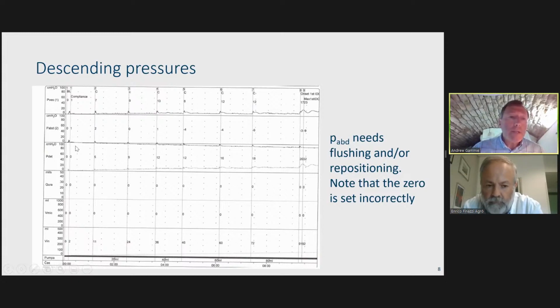But the point here is that it can also be seen that the abdominal line is descending slightly. Even though these little coughs are being picked up, the background resting pressure is going down. But our patient is not losing weight. There's no change inside them that is suddenly decreasing the pressure. So there's a problem. And for quality control, you've got to recognize that. And in this case, if it's a water-filled system, the abdominal pressure line should be flushed, just to restore the water inside the balloon that connects with the rectal cavity. Sometimes you can just reposition it, actually. So when we have this descending pressure, you've got to make sure, if you see it, that you rectify it, because the pressures are going down. That's during the filling phase. Can it happen during voiding as well, Enrico?